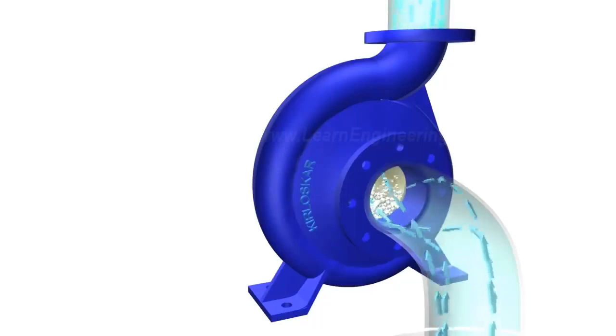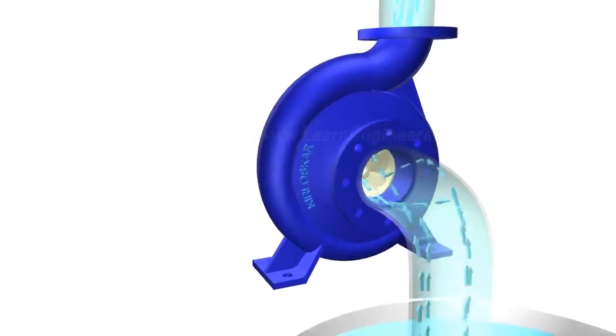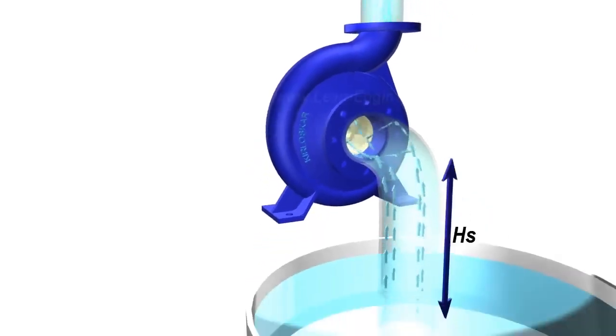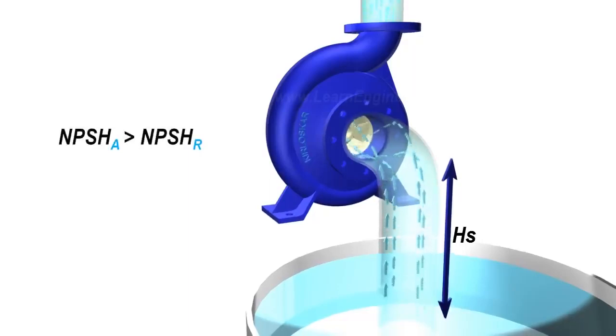This phenomenon is known as cavitation. More the suction head, lesser should be the pressure at suction side to lift water. This fact puts a limit to maximum suction head a pump can have. Careful pump selection is required to avoid problem of cavitation.